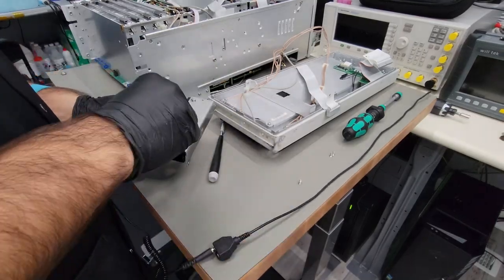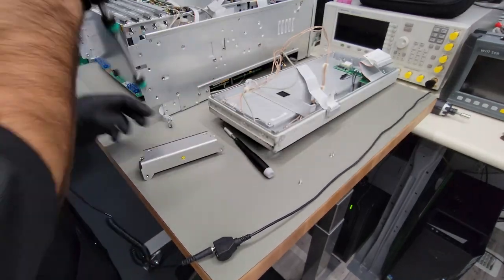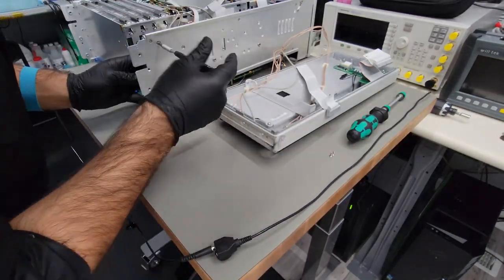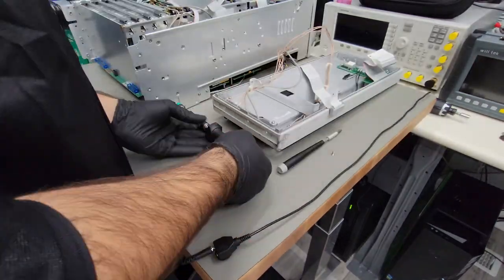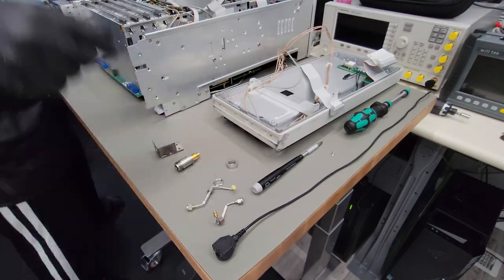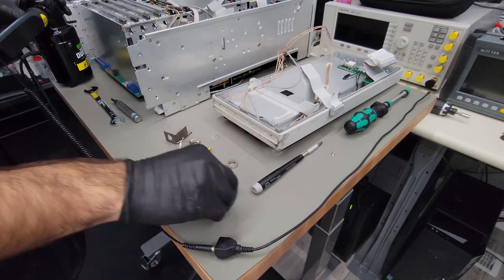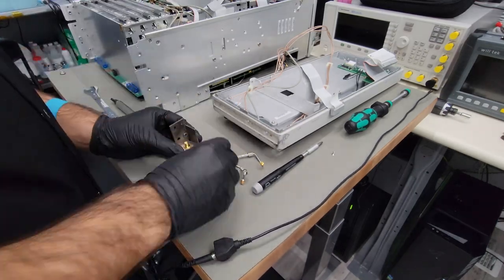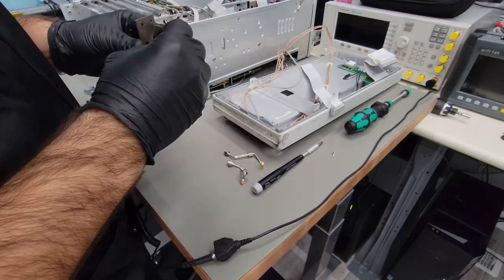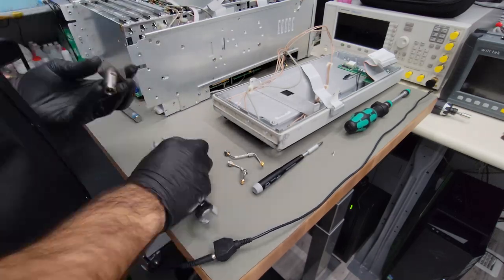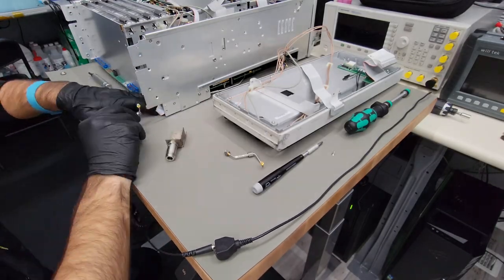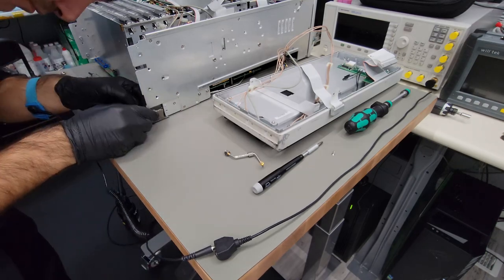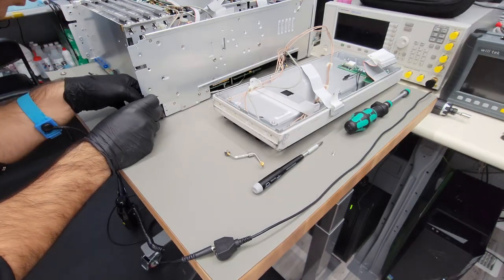So now that I know that the front panel connector and the attenuator are no longer an issue, I'm just going to go ahead and reassemble all the hardware on the front panel and get the front panel back on the instrument. This will make it a lot easier for me to manipulate it and move it around. The PSG, as far as the mechanical chassis goes, a lot of the rigidity does come from the front panel, so you don't want to really move it around a lot without having the front panel bolted on.